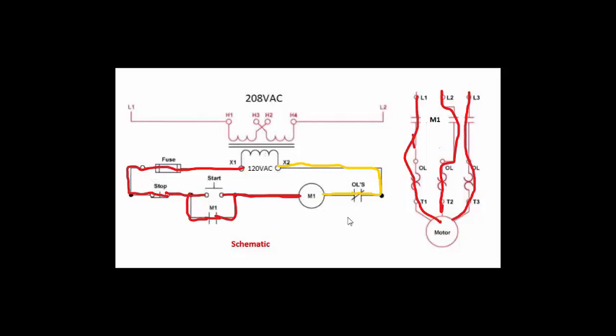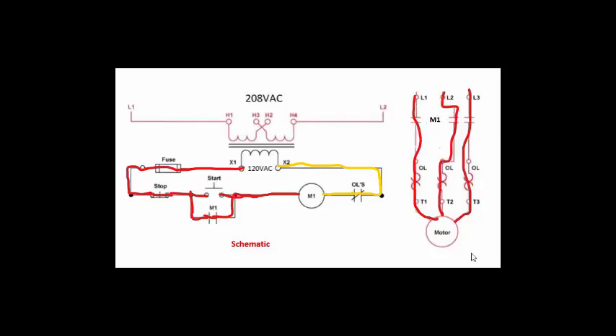or if there's loss of power, or if these heaters get too hot and this overload contact opens up, and then the motor will stop running. So an example would be if the stop button is pressed, we open the circuit here, and this is no longer going to be energized. This contact will open, and these contacts will open as well, and there'll be no power going to the motor. Another possible scenario would be the overload relay here. If one or two or three phases got too hot, then this contact would open up, and then there would be no power to the coil, and that's also going to open up this contact, and it's going to open up these three contacts, and then the motor would stop as well.